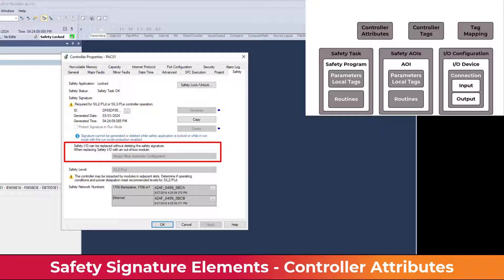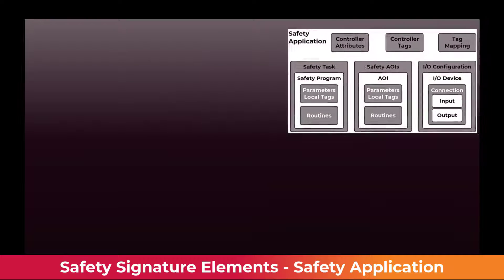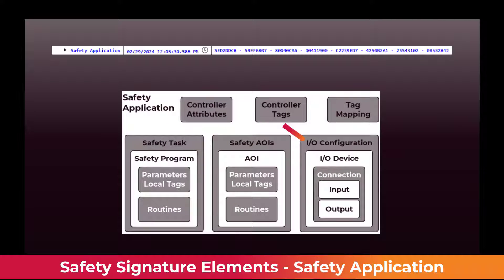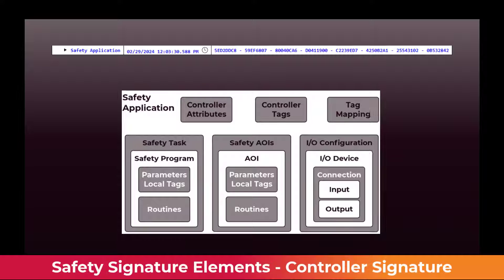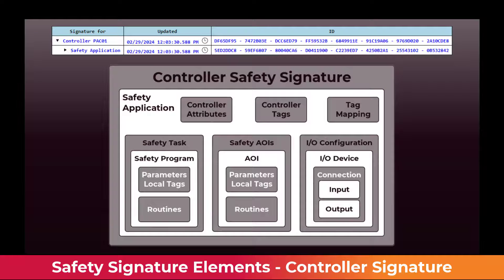The safety application signature includes the Safety IO configuration, safety add-on instructions, safety task, tag mapping, controller tags, and controller attributes. The controller safety signature encapsulates all safety-related software in the controller.